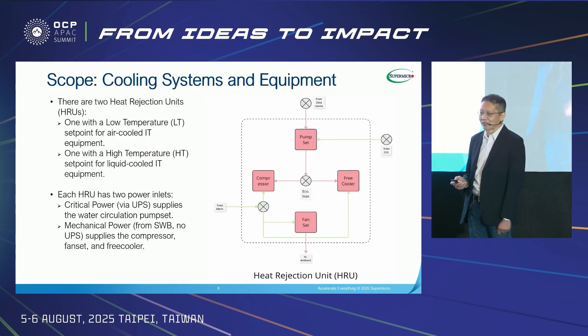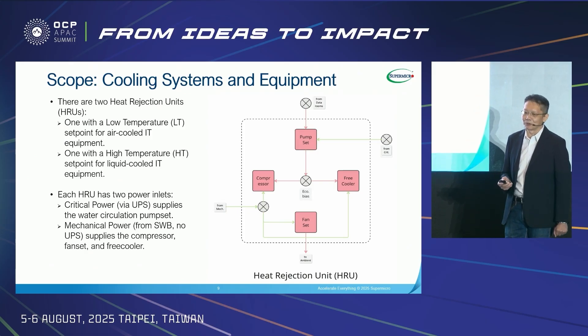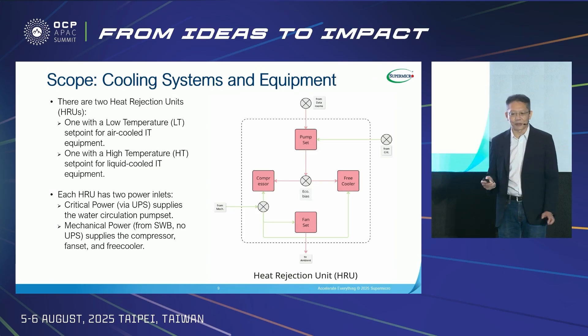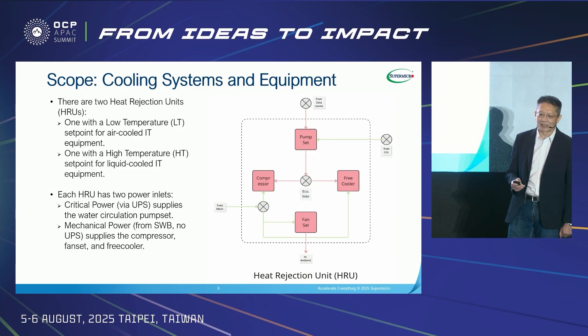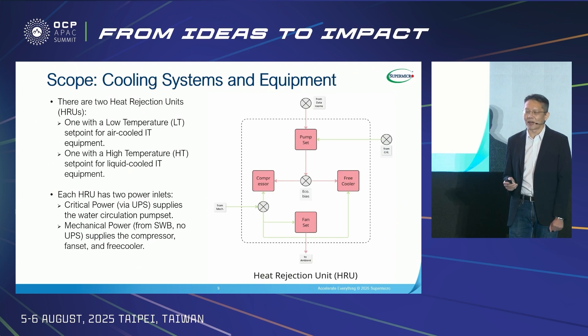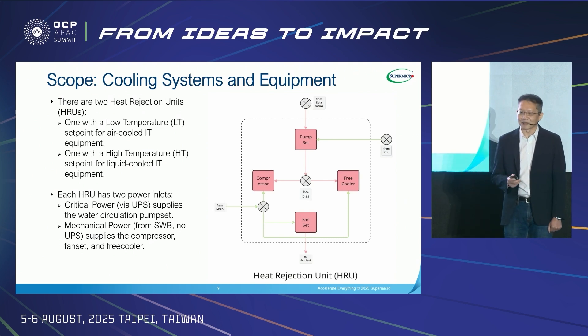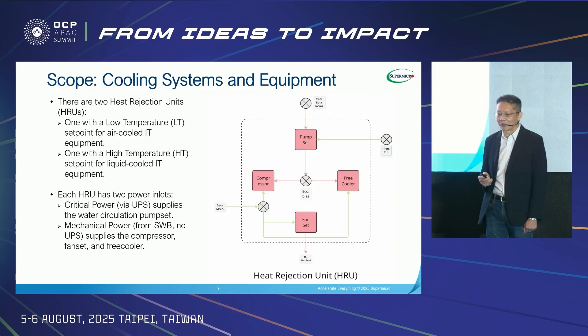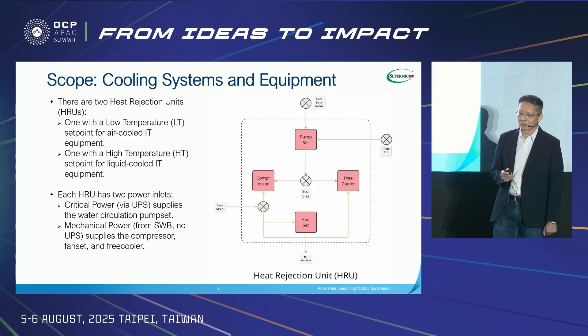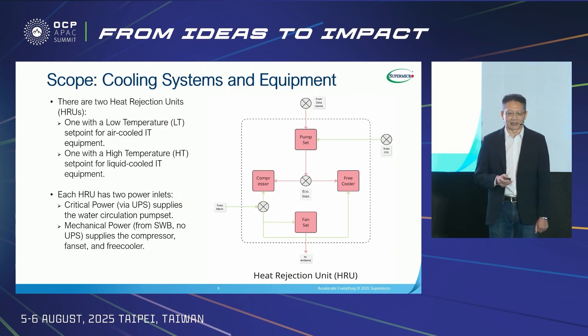There are two HRUs: one with a low-temperature set point for air-cooled IT equipment and another with a high-temperature set point for liquid-cooled IT equipment. Each HRU has two power inlets — one from critical power to feed the pump set for water circulation, and one from mechanical power to feed the compressors, fan sets, and free coolers. Cooling equipment is selected based on air and liquid cooling configurations.